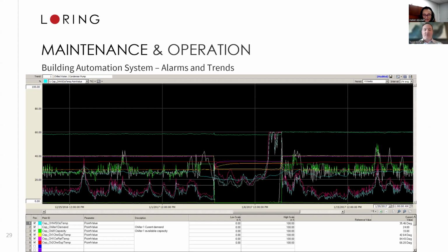This is a whole data stream where we're taking those individual points out in the system that are being monitored, say chilled water temperature, pump speed, anything else that's related to energy consumption, and watching how that functions over a period of time. We can see this is about 3 weeks' worth of data from a single chiller in that plant, where we're able to see and track how well this individual piece of equipment is running. And there can be hundreds of pieces of equipment in a building. Each of them is going to have its own separate trend.